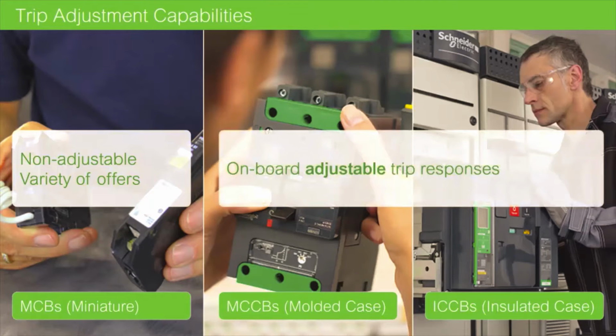Our molded case and insulated case circuit breakers do offer adjustable tripping by electronic means, and in some molded case circuit breakers rated 250 amps and over, there is adjustment that can be made to the magnetic trip as well. The means by which the tripping can be adjusted will be addressed more in the upcoming courses on molded case and insulated case circuit breakers.